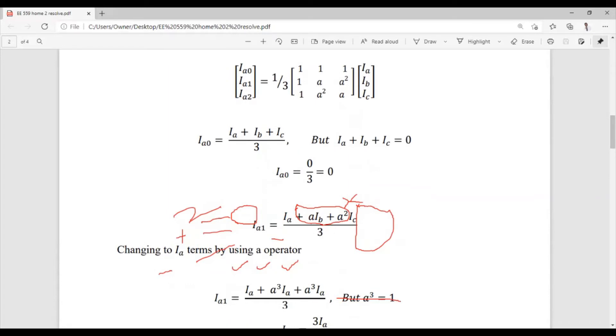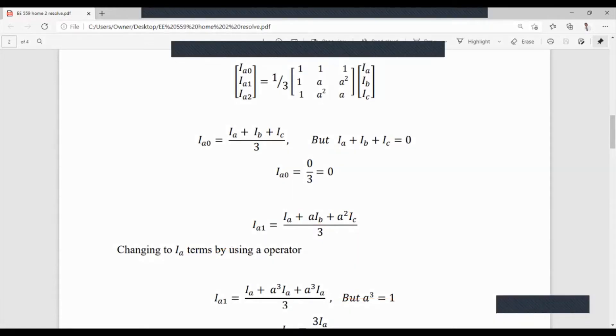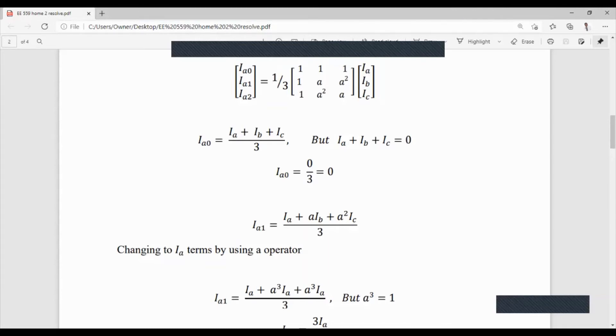Since there is no zero sequence current flowing in this fault case, if you set your relays or circuit breakers to detect zero sequence current in order to trip, they will not operate — because there will be no zero sequence current for them to detect.